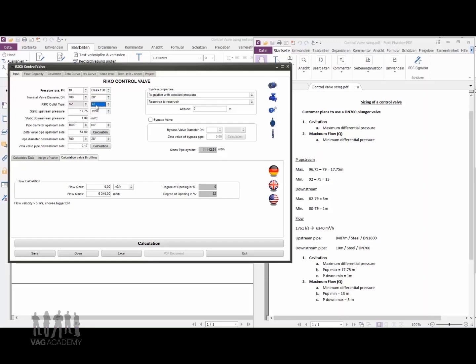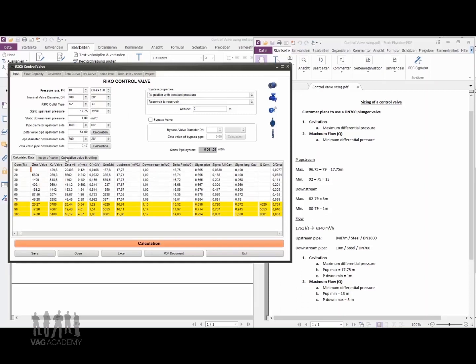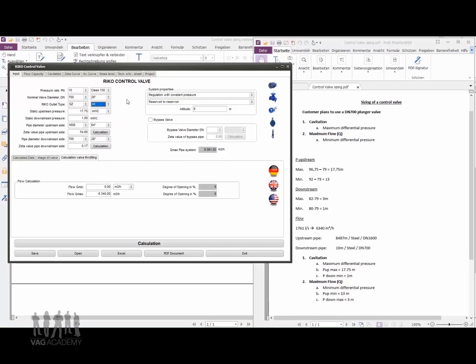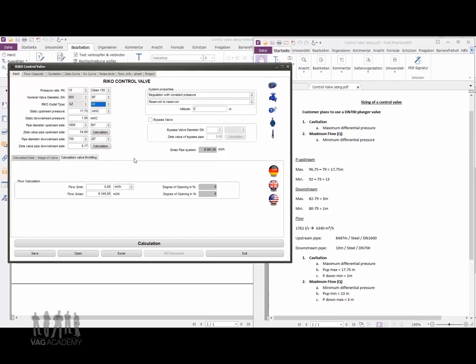I change my cylinder to SC40 and hit the calculation button again. I can see the cavitation message is still there and I'm not able to achieve my maximum flow. So I'm in the dilemma that with the highest flow-capable cylinder, I can't achieve the required flow and I'm still within cavitation. This indicates that the valve size is too small. Therefore, we would recommend a larger size. I will go with a DN900 and stick with my SC40 cylinder as I'm fairly close to the flow requirements.